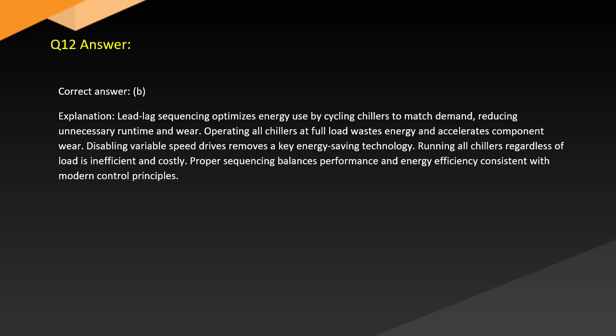Answer: Correct answer B. Explanation: Lead-lag sequencing optimizes energy use by cycling chillers to match demand, reducing unnecessary runtime and wear. Operating all chillers at full load wastes energy and accelerates component wear. Disabling variable speed drives removes a key energy-saving technology. Running all chillers regardless of load is inefficient and costly. Proper sequencing balances performance and energy efficiency consistent with modern control principles.